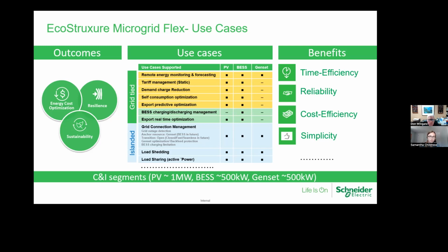So certain customers might say, hey, I want everything in my building to be backed up. That's achievable, but you might have to upsize your distributed energy resources to get full building backup. Other customers say they don't need 100% of their building running during an outage—that helps save on battery storage and diesel fuel, so they'll only use 30% of the building. That load shedding can be configured based on the site's needs.